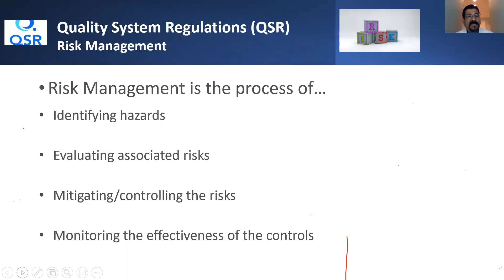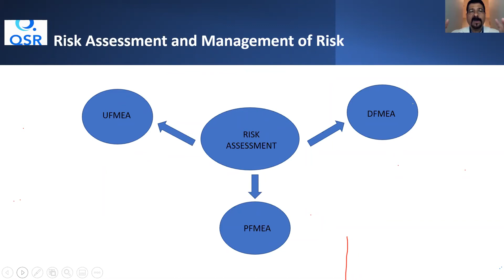It's called FMEA. The FMEA is used very widely in the med device or the drug device combination world, and various types of FMEAs are there. There is the user FMEA, which you do for the user. You do design FMEA for the design of the device, and you also perform the process FMEA, that's called the PFMEA. So user risk assessment is called user FMEA, the design risk assessment is called design FMEA, and the process risk assessment is called the PFMEA. This all falls under the category of risk management, which is a critical part of the design control.